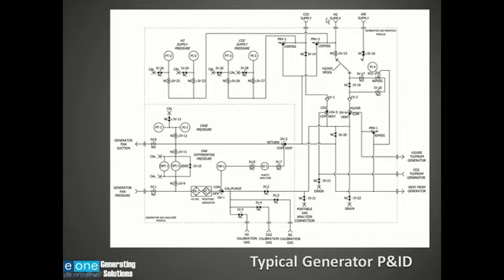Here we have the hydrogen supply pressure. Again, we have a pressure relief valve. We have a local pressure indicator to tell us what the hydrogen supply pressure is. We have, again, a pressure transmitter that is feeding the signal back to the control room. And again, we have the cal ports and the isolation valves so that these can be calibrated. On this particular unit, under normal operating conditions, we have a pressure control valve that will maintain the pressure in this generator at 60 psi.